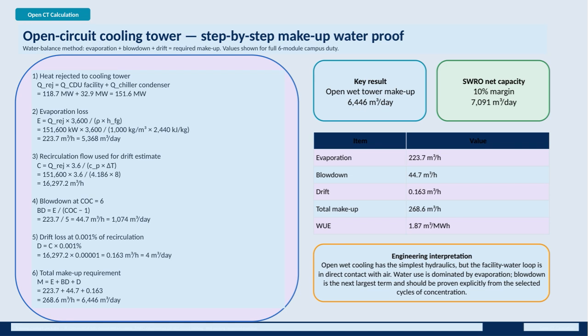Starting with heat rejected to the tower, we combine the facility heat load and the chiller condenser load to get 151.6 megawatts. From this, evaporation loss is calculated using the latent heat of vaporization, resulting in 223.7 cubic meters per hour or 5,368 cubic meters per day. Next, we estimate the recirculation flow used to determine drift losses, arriving at around 16,297 cubic meters per hour.